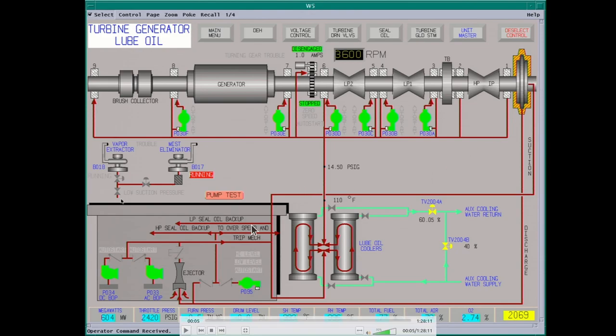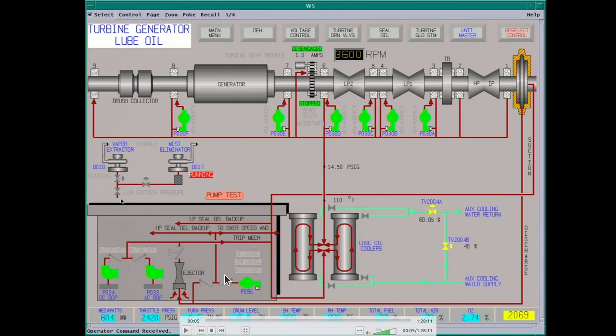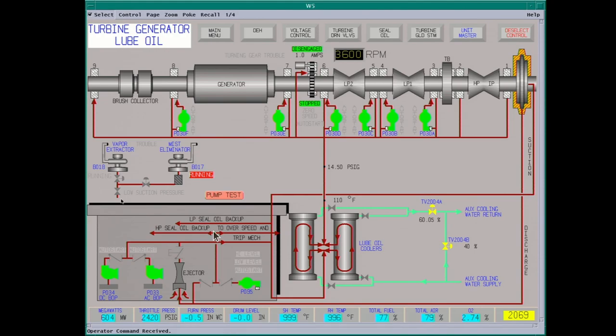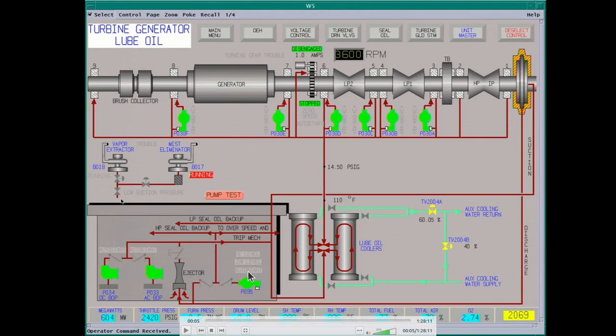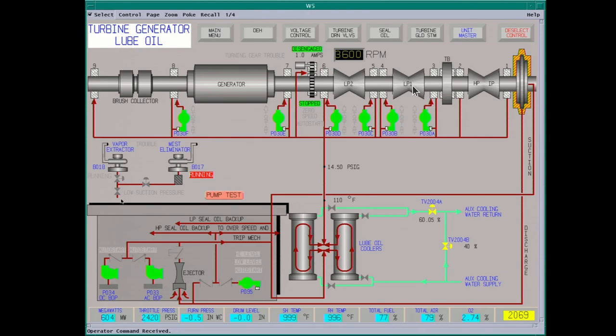The lube oil tank is on the first floor; the turbine is on the third floor. Some of the high-pressure oil is used for seal oil backup for your hydrogen seals, the overspeed, and a few other items. The bearing lube oil goes through the lube oil coolers and then it's fed out to all the bearings. This unit has an intermediate pressure turbine, high-pressure turbine, and two low-pressure turbines. Each low-pressure turbine has its own surface condenser hot well.